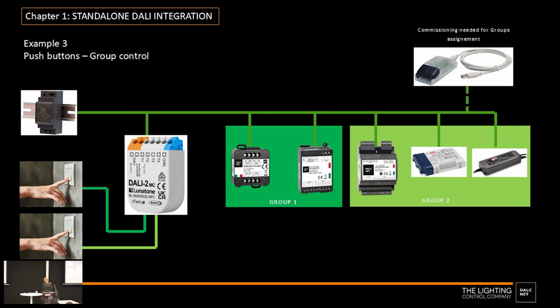I have to assign the group to every device. So if I want some devices under group 1 or push button 1, I need to address those devices to group 1, and the other devices to group 2. Then the system—I can disconnect the programmer and the system can work without any other input, just with the push button controlling directly the control gears.